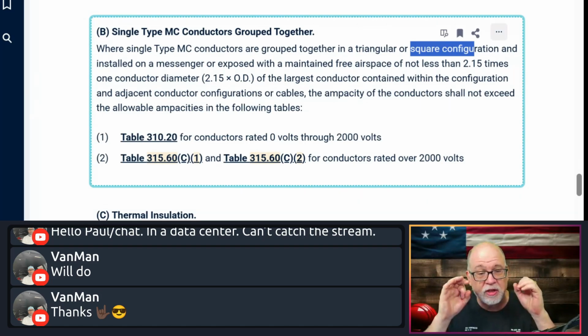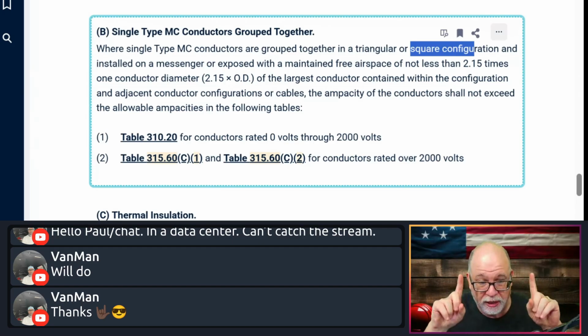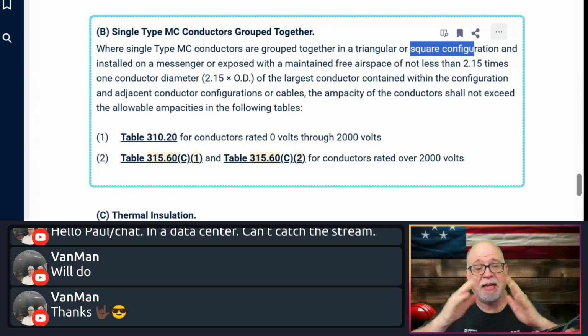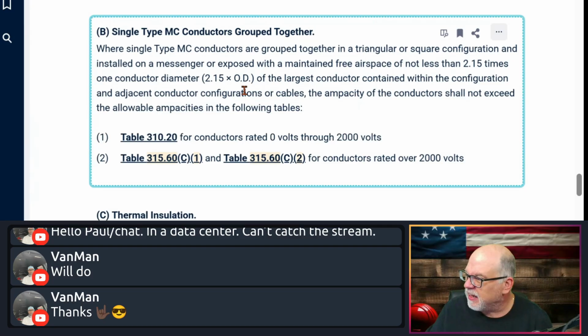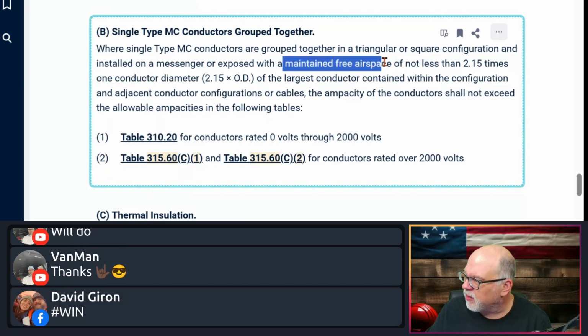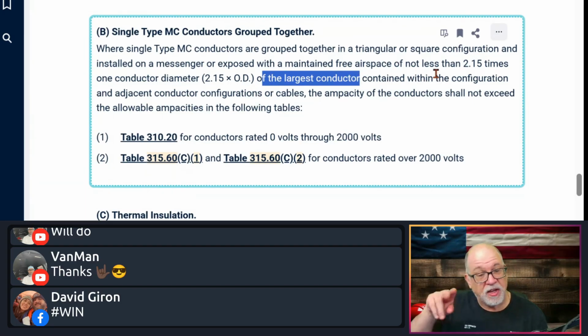Okay, these are single conductors. You have to tie them together so they act as one. Okay, you don't get any wild magnetic fields and things like that. Okay, it says, and it says grouped together in a triangular or square configuration and installed on a messenger or exposed with a maintenance-free airspace, a maintained airspace of at least 2.15 times one conductor diameter. So it's 2.15 times the OD of the largest conductor contained within the configuration.